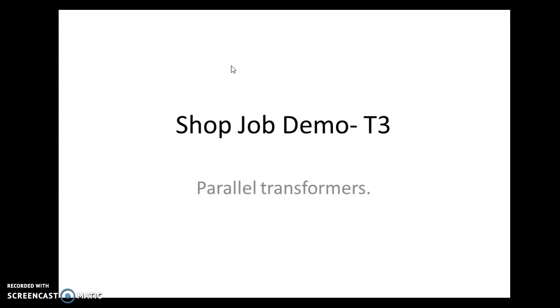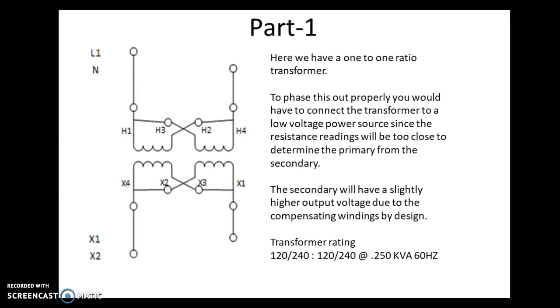You should have reviewed the paralleling operation PowerPoint for this lesson before trying to do the ShopJob. Part 1 here, we're just going to reiterate that to phase out a transformer that has a 1-to-1 ratio properly, you should connect it to a low voltage power source to determine what is the primary or the secondary coil. Keep in mind the secondary side will have compensating windings by design, and the voltage from the low voltage power source will appear to be slightly higher on the secondary side as opposed to the primary.